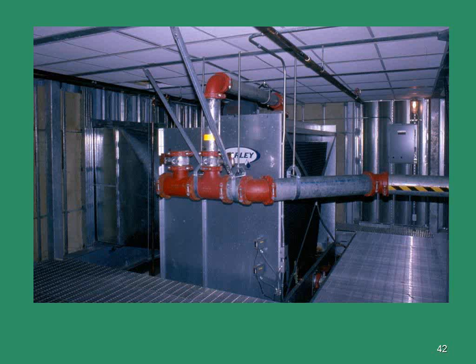Question: is there an advantage to using thicker lining, say 1.5 inches versus 1 inch? Inside an enclosure, yes, thicker lining helps absorb more low frequencies, since lower frequencies have very long wavelengths, and the thicker the lining, the more of the lows you absorb. But there's a practical limit, it's probably a nickel solution to a dollar problem, it won't fully solve the issue. Sometimes I'll tell a mechanical designer we need 1.5 inch or 2 inch duct liner, and I regret it, because he needs an inside diameter to move air, so a 2 inch duct liner eats up 4 inches in both dimensions, which can be a real problem in most buildings.